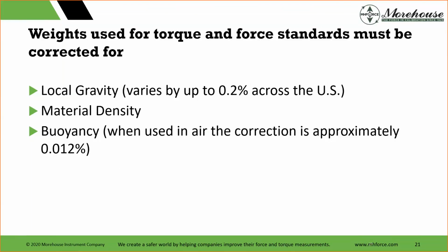The additional notes, the elevation of each weight should be considered. If you had a really large stack, chances are no one's doing super large torque with a lot of weight, because we'd all hear about it if somebody could do 500,000 pound-feet. Material density, knowing the density of the material from which the weights were manufactured. That goes into the equation, which I'm going to show you. Buoyancy, the Archimedes principle applies. Air pressure under the weights causes an upward force. This reduces the effective force generated by the weights, and therefore the mass must be increased to allow this. When used in air, the correction is approximately about 0.012%.